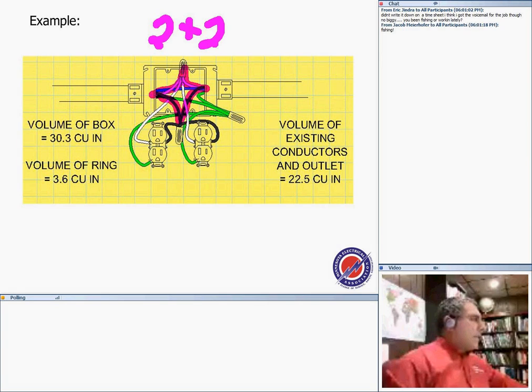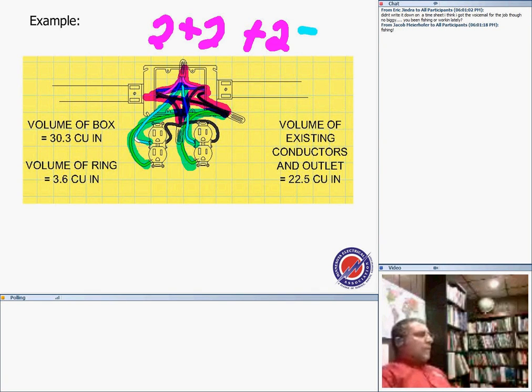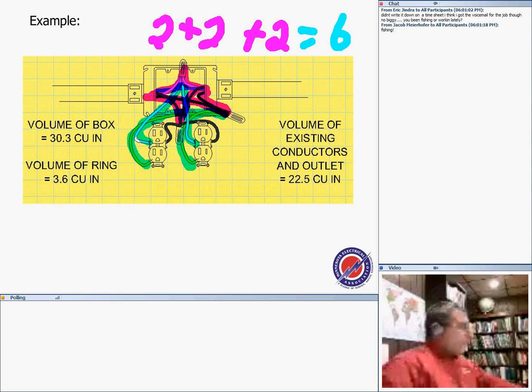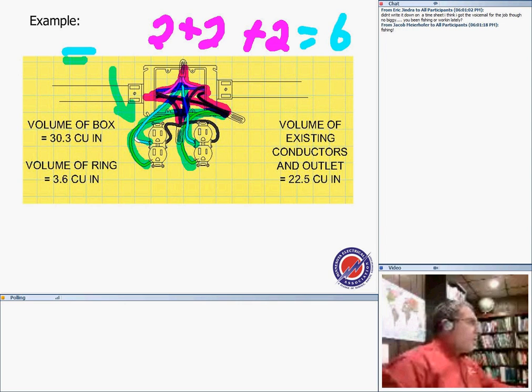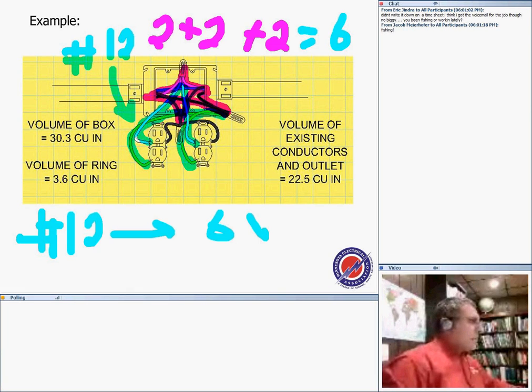Okay. And since I'm pulling an isolated ground, this counts as 1. Here's 1, here's 1 out, plus 2 for isolated ground. All pigtails count as 0. So this piece here, the piece coming to here, the piece going to here, and all pigtails, and another piece picking up the neutral and the ground, all these count as 0. So this really has 6 conductors. Okay? All these conductors were number 12, let's say, for the cover.